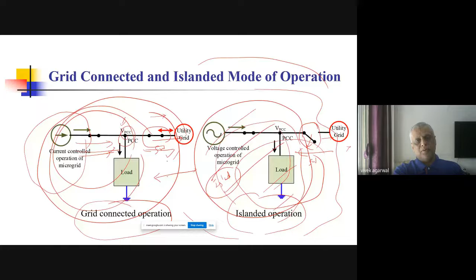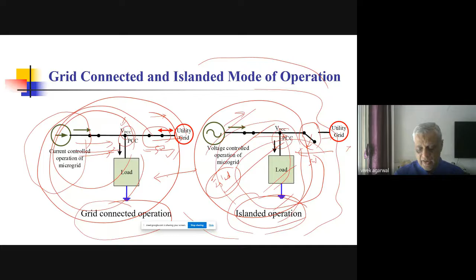But here in the islanded operation, because the grid is not there, there is nobody to regulate. So first of all, you need to have your own source to regulate the voltage and frequency on the microgrid bus. That is one very major problem. The other is that you do not have any surplus or deficit reservoirs, and hence you must resort to load shedding.